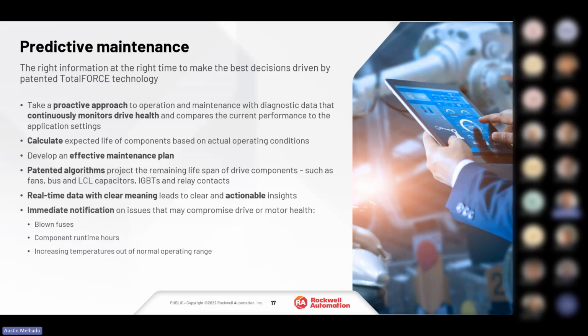So with that, it will calculate the expected life of components based on actual operating conditions and real-time information, allowing you to take a proactive measure, help reduce unplanned downtime, and develop an effective maintenance plan. With the patented algorithms projecting the remaining lifespan of drive components such as fans, bus and LCL capacitors, IGBTs, and relay contacts, contextualization of real-time data from the most advanced set of onboard sensors leads to clear, actionable, and full diagnostic and predictive analytic insights.